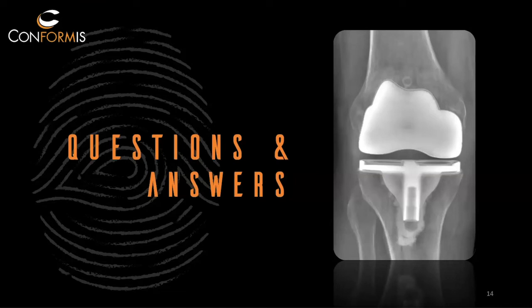One thing we didn't discuss much is the titanium tibial base plate. I really like the feel of the titanium — it is lighter, which I never thought I would perceive, but I was pretty impressed. The cement rail is rock solid, and the dovetail in the cement rail makes a nice benefit, as does moving it out to the periphery, which will increase the overall cement mantle. The tibial keel and post being longer and bigger — just like the PS — is also a real value-add. Still the same great surface technology matching the articular surface to the anatomy, but mostly improved tibial fixation with the identity.